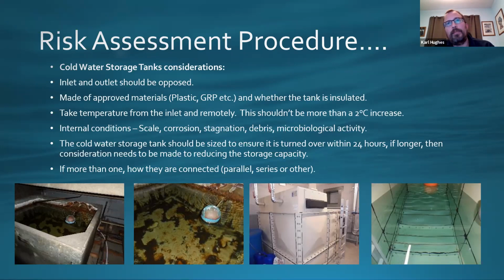If there is, then it could indicate anything from a lack of cross flow, so the inlet and outlet aren't opposed, or that the tank is too large a capacity for what's needed. You'd make a note of what the internal conditions are. You can see on the left-hand side you've got quite a lot of corrosion debris in there, a bit of scale around the inlet, any debris and things like that, or any microbiological activity. You can see the one on the left-hand side has no lid on it, so you need to make sure there's a close-fitting lid on there to stop anything from getting in. Luckily in this one, nothing has actually made its way in and died in there, which we've seen plenty of in the past.